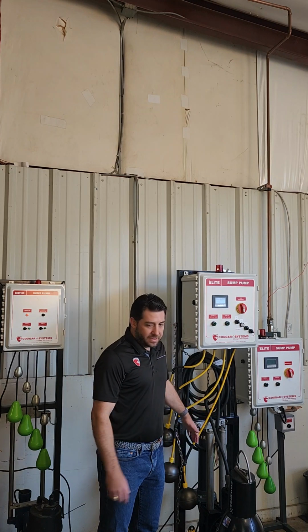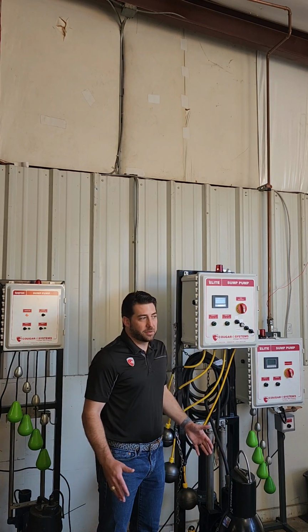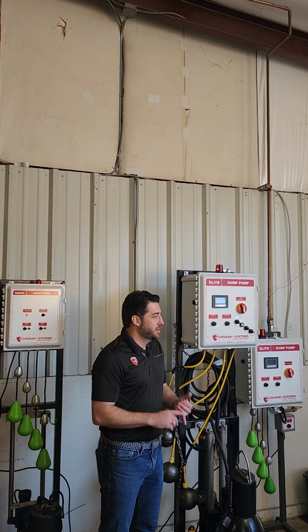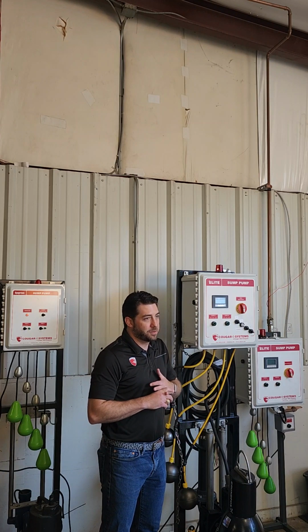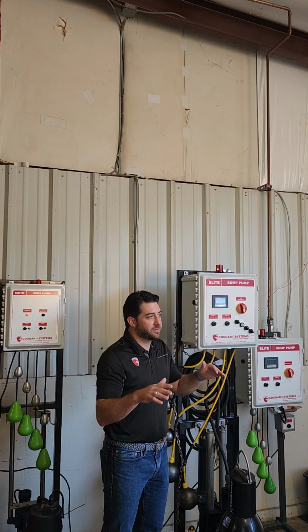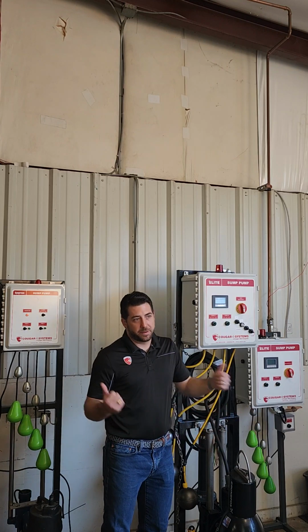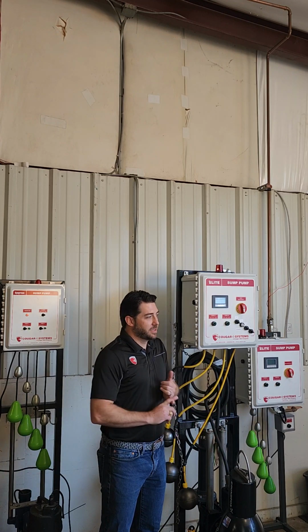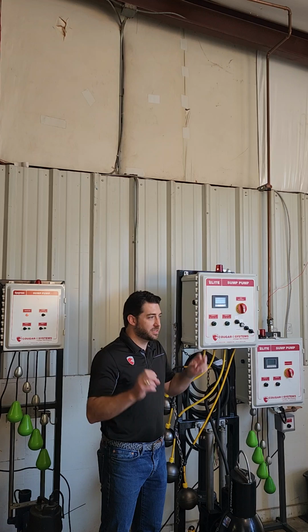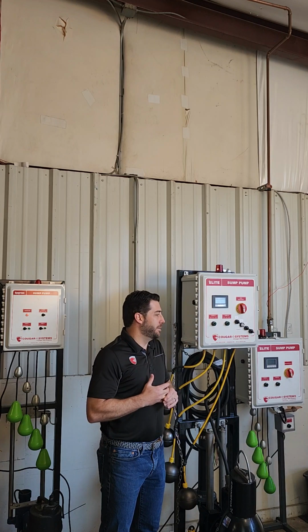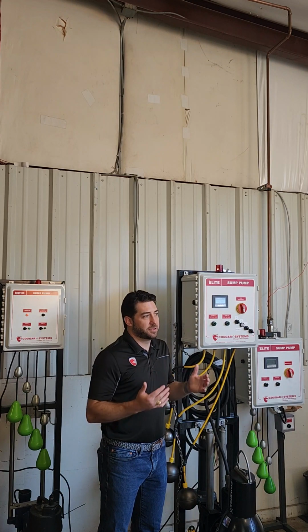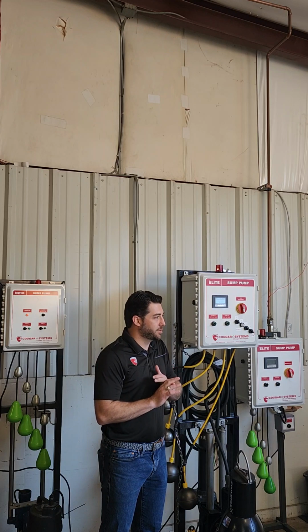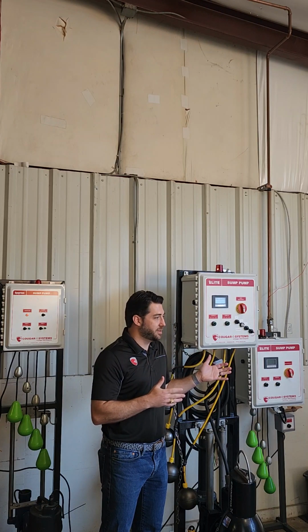So basic kind of application, the whole point of these things: anytime you have drainage or fixtures below grade, where you can't gravity drain away from the building, you're going to have to collect it and pump it out with these, right? So it's going to be either storm or sanitary. Storm is somewhat clean, and then the sanitary is going to be anything after use. So fixtures, grease traps, anything like that's going to be sanitary.